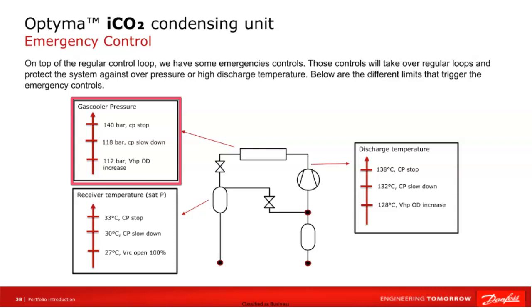Protection against excessive pressure in the liquid receiver works similarly. When the temperature reaches 27 degrees Celsius, the bypass valve opens completely. An increase in temperature to 30 degrees Celsius causes the compressor to slow down. And after exceeding 33 degrees Celsius, the compressor is completely turned off.